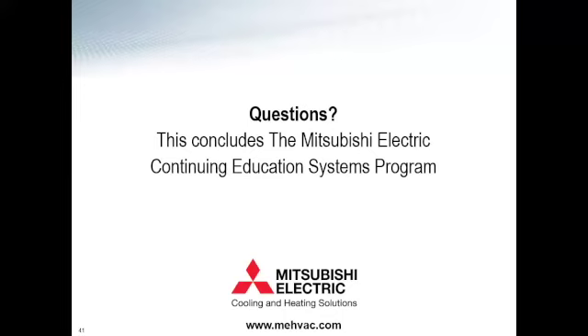We are working on a bunch of products, and we actually do offer products in Europe and Asia that work on different refrigerants, not R410A like we offer in the United States. But the main answer that Mitsubishi is thinking about for the United States as it looks at some of the larger projects is we're moving towards an HVRF technology. So actually what that's going to be, and I don't want to spoil too much for everybody here, I don't have a release date on this, but within the next year, we should be able to provide a system that is only going to be refrigerant from the condensing unit to the BC controller. From the BC controller to the rest of the space is going to be water in the piping. So that really alleviates all of your ASHRAE 15 and 34 issues.